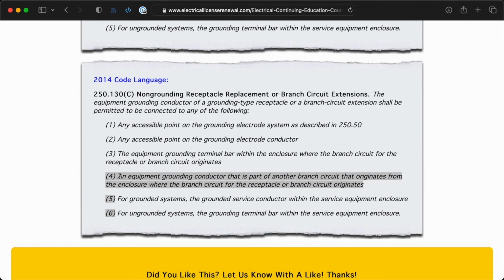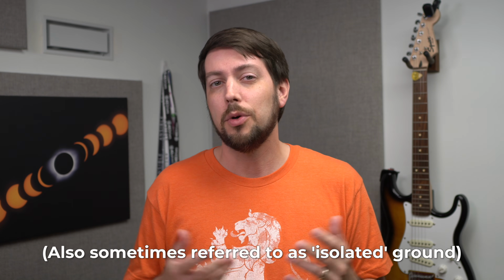And the independent grounds are helpful for some scenarios where I need a clean electrical signal. A lot of times in commercial installs, to save on wire pulls, electricians will share a ground between 2 circuits. The 2014 NEC code actually allows this. Before you comment otherwise, go read section 250.130c.4.